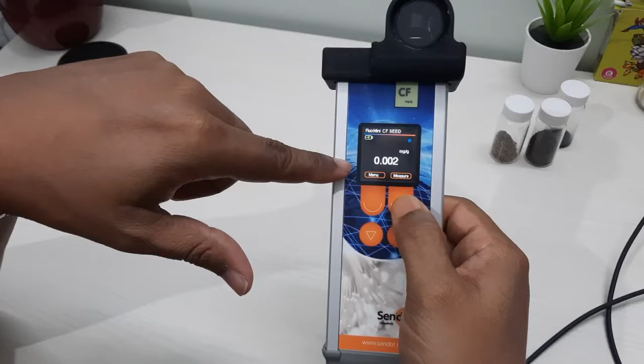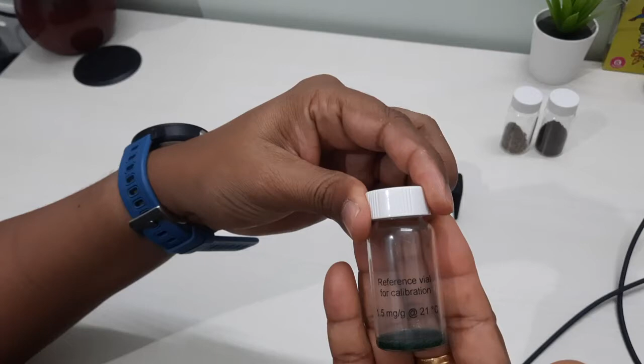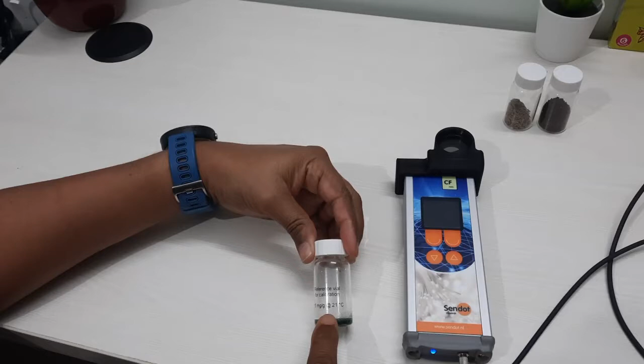Now coming to calibration. First you have to refer to this reference vial, which will be showing 1.5 mg per gram at 21 degrees centigrade. This is the reference vial, which you have to put on top of the sensor, and you have to measure it. If the measurement is coming to 1.5 or 1.6, then the machine is almost calibrated. Here we can see that the measurement is coming as 1.6, so it needs to be more accurate, and it needs to be calibrated once more. So this is how you measure it.